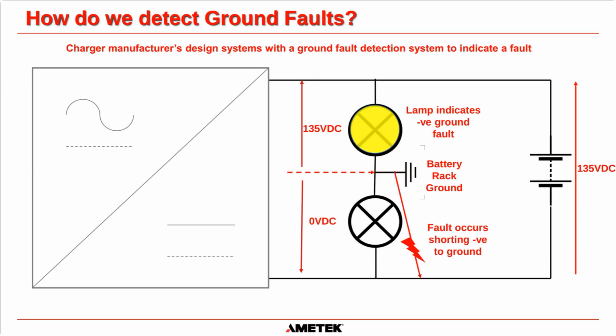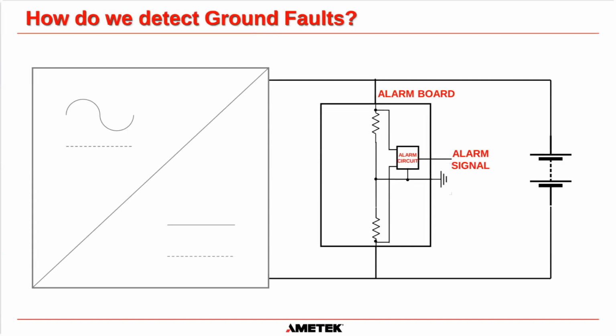And that is why on nearly all industrial systems, you will find that the voltage between the positive to ground and negative to ground is halfway between the battery voltage. So for a 135 volt system, it's 67.5. That's for 60 cells lead acid. For 120 cells lead acid, it's going to be 135 volts positive to ground, 135 volts negative to ground. Okay, it's just basically a ratio of half. And in truth, that was in the olden days, the lamps, a very simple, cheap circuit.